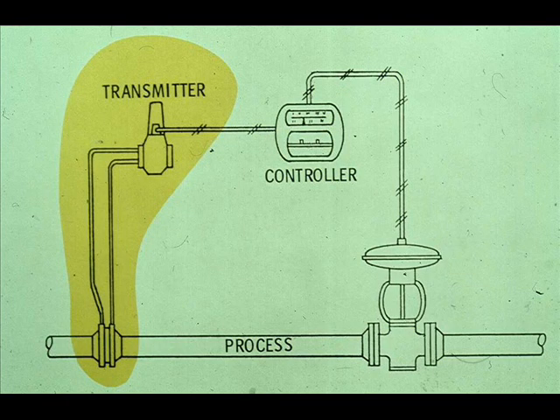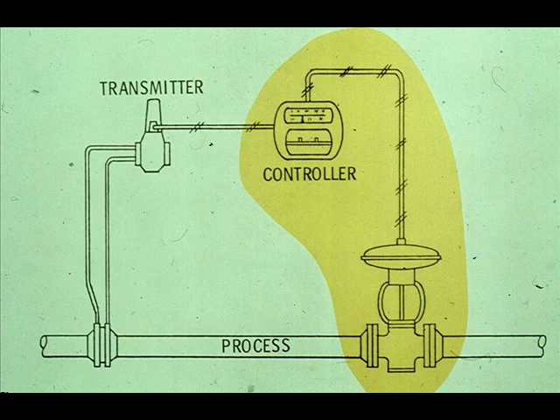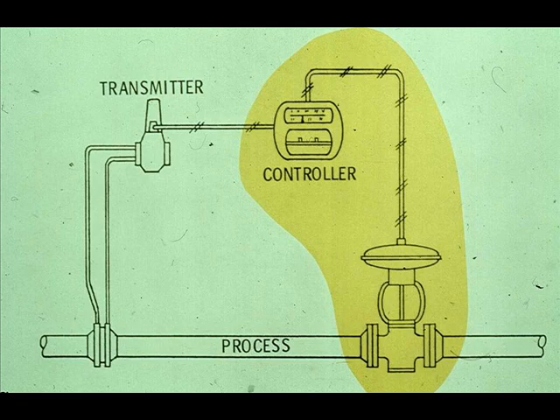The delta P measured by the orifice plate goes to a transmitter, which converts the measured delta P to a signal which is proportional to the delta P. This signal goes to the controller. The controller compares this measurement to the desired measurement, called set point, then computes a control signal which goes to the control valve. The control valve will then open or close as necessary to keep the flow rate at the desired point.